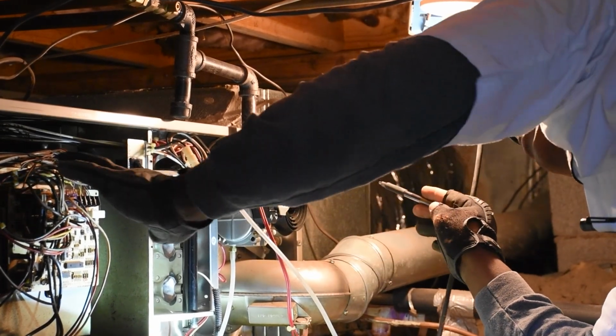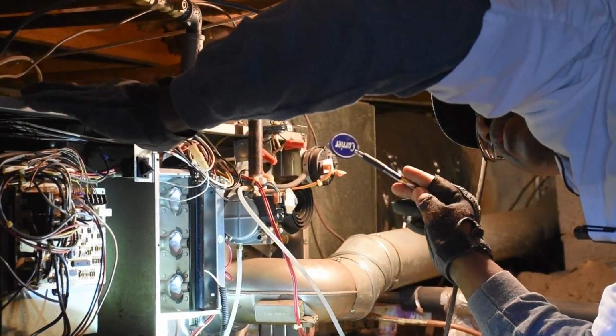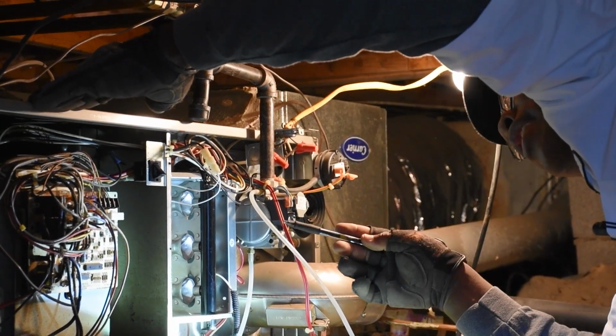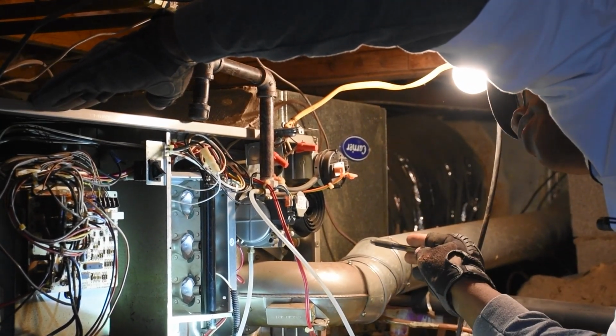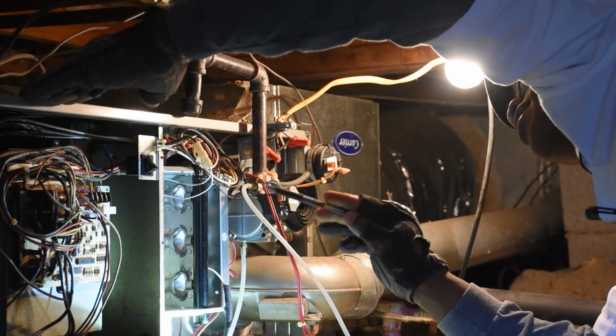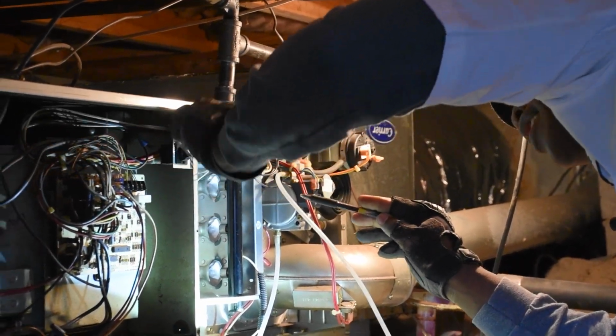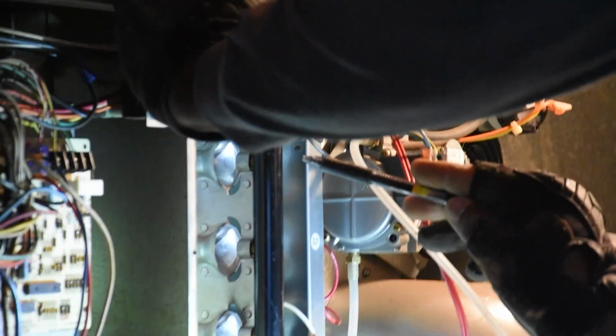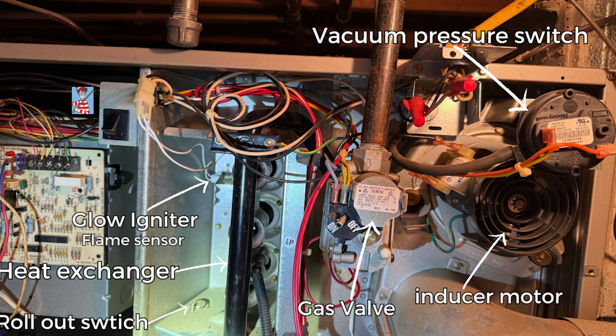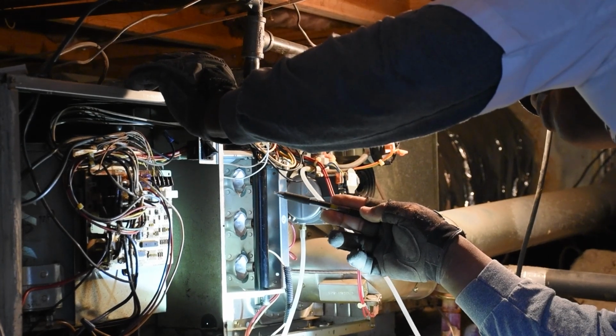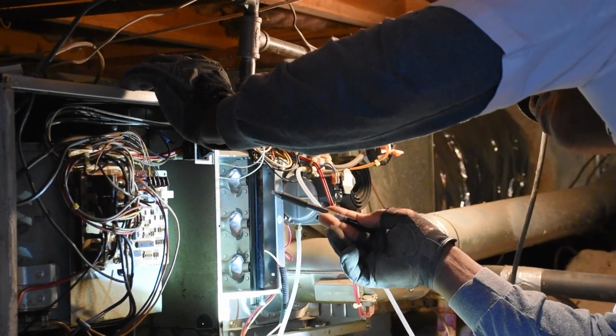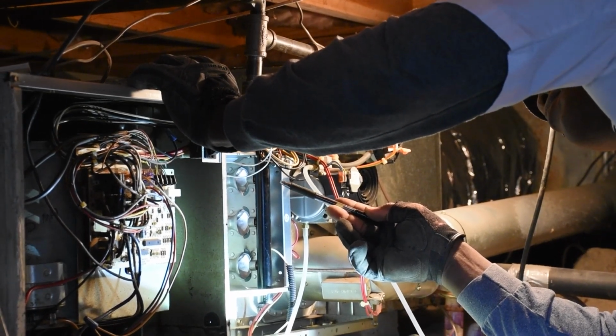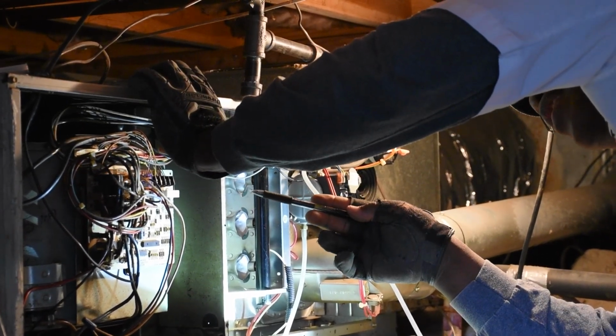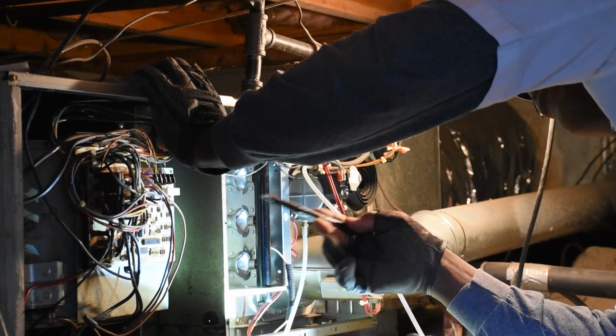Once the control board gets the signal that all is cleared, my flue is cleared, it sends a signal to this device, which I don't know if you can see in here, called a glow igniter. Once the igniter starts glowing or sparking, it tells the board, okay, I have spark or I'm glowing.